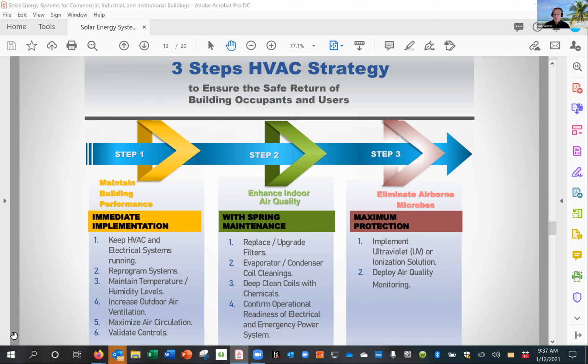That's the equivalent of what we call a commercial building air filter compared to a MERV 13. So when Governor Cuomo said one size fits all, put in MERV 13s, what he was suggesting was not really a good HVAC strategy, because not every system is designed to move air through a filter that traps as much stuff in the airstream as a MERV 13 filter. MERV 13 filters were basically designed for operating rooms or laboratories where there were fumes in the air and things like that. If you Google MERV ratings, you can see a whole rating for different filters and what they actually remove from an airstream.